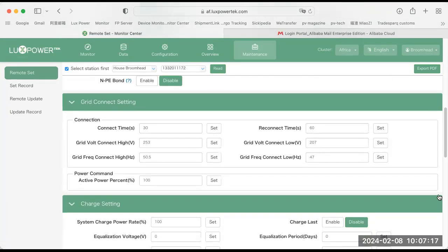The grid connect setting, I think we've gone through this in the training before, but this is purely where you as an installer can set it. It comes pre-populated like this, and this is simply your connect time. So for instance, when the grid goes off and when the grid reconnects, it shows you how fast the machine will switch from off-grid to on-grid mode. And the other one is for the PV, especially if you've got export to grid activated, it will show the delay time for reconnecting.